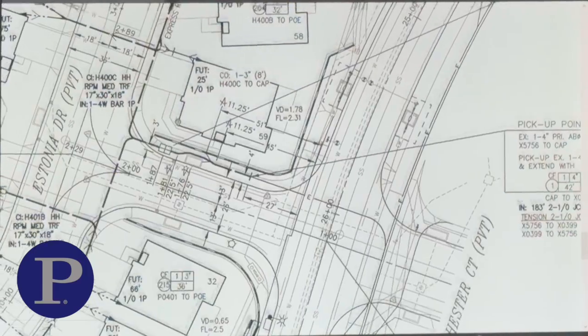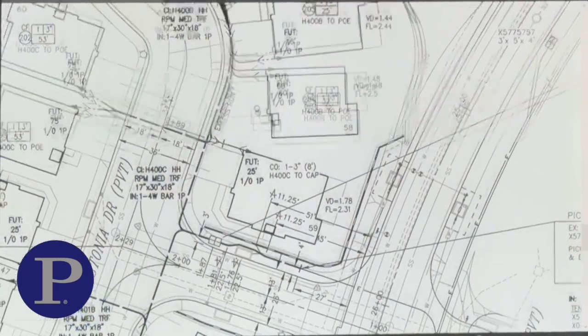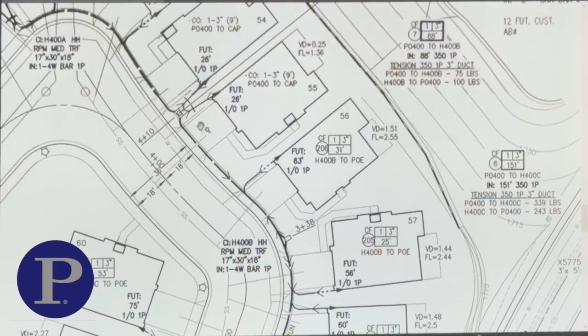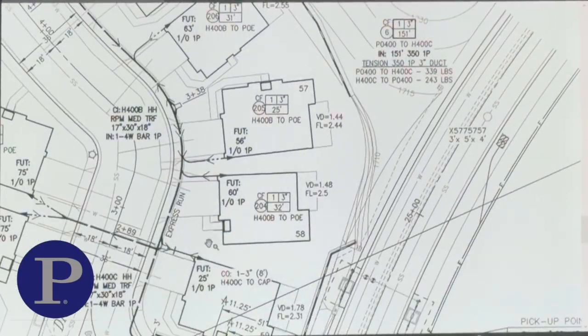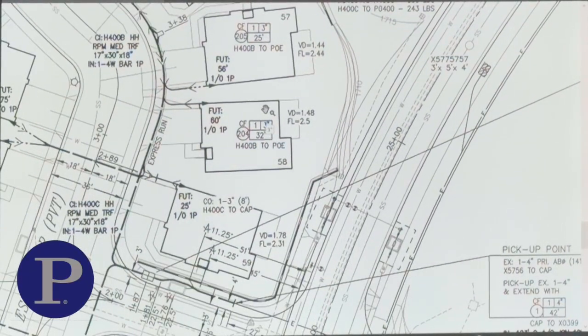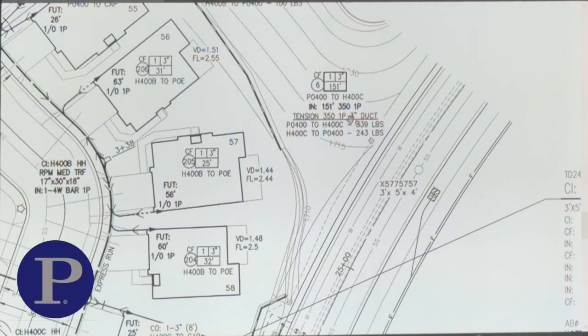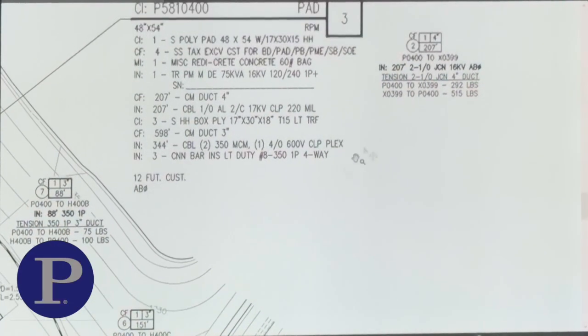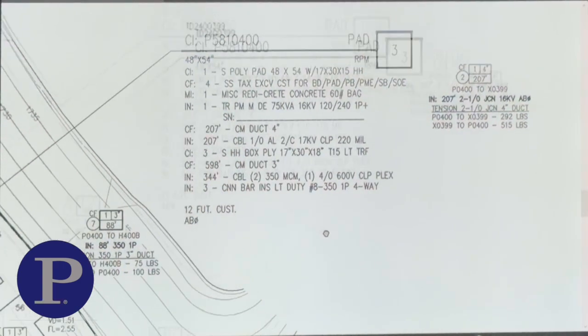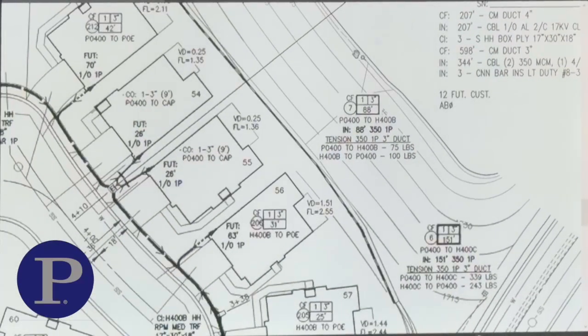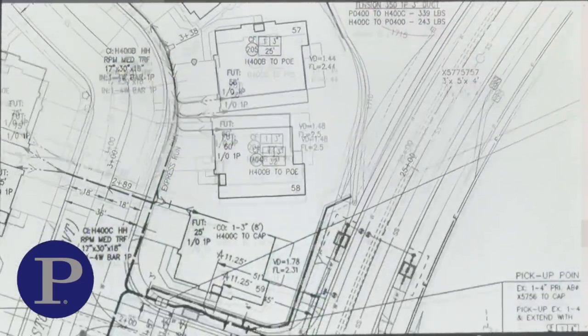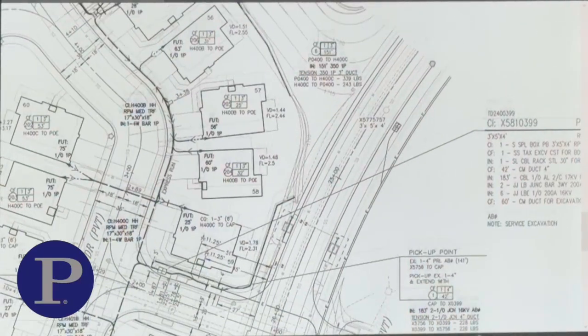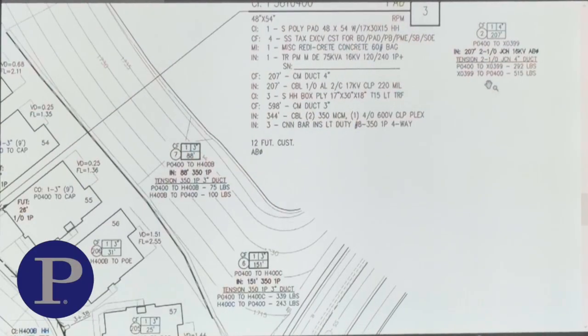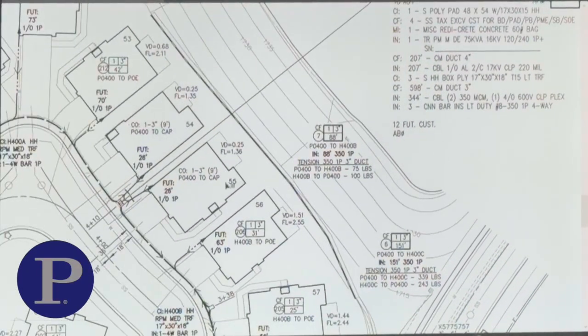From this pull box, we're going to come up here, and we know that that's going to feed to another transformer. So here's my transformer right here, feeding from that new pull box. There's going to be a call out right over here somewhere, 207 feet. And we know that this is the call out because we've got pad 400 to splice box 399. This is our pad 400 right here, and that's feeding from this pull box right here at 207 feet, 2 conductor, AB phase.